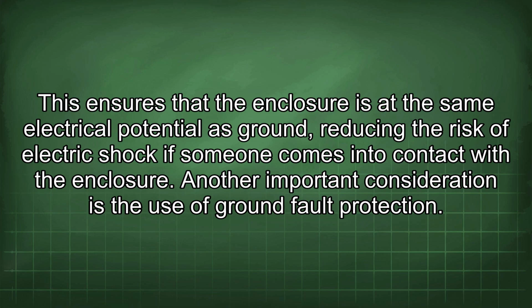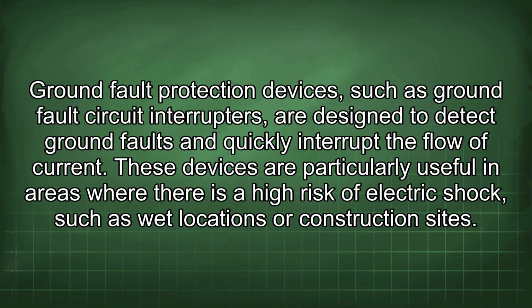This ensures that the enclosure is at the same electrical potential as ground, reducing the risk of electric shock if someone comes into contact with the enclosure. Another important consideration is the use of ground fault protection. Ground fault protection devices, such as ground fault circuit interrupters, are designed to detect ground faults and quickly interrupt the flow of current. These devices are particularly useful in areas where there is a high risk of electric shock, such as wet locations or construction sites.